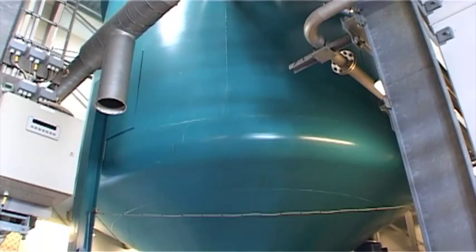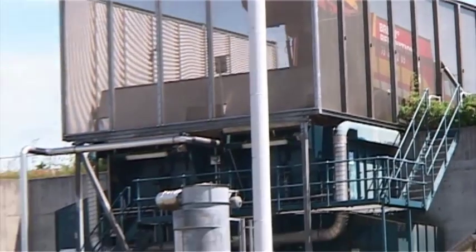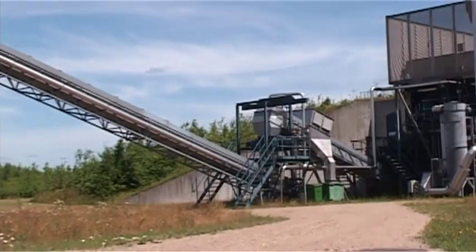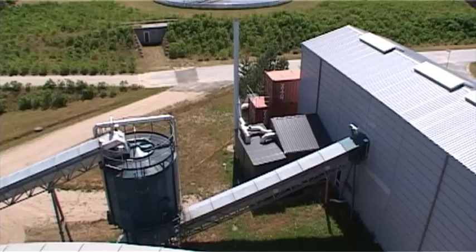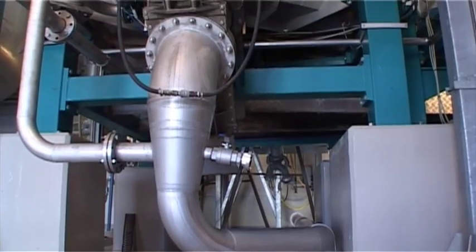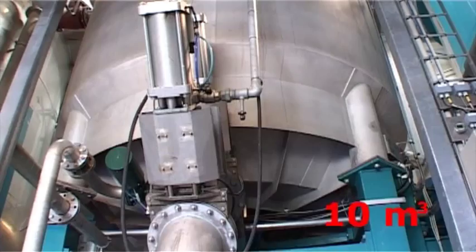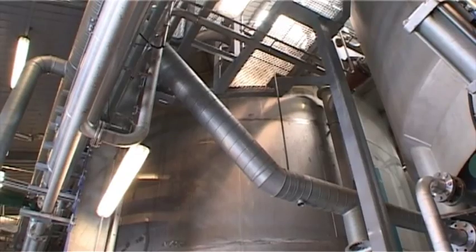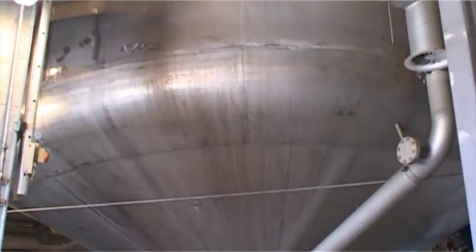Sewage slurry is pumped in from this tank. Food refuse is broken down in a two-phase process, which also involves magnetic separation. The processed refuse is then stored in a buffer tank, from which the precise amount needed can be transferred via a computer-controlled belt conveyor. Liquid industrial refuse is pumped from the industrial reception tank by injection into the mixed pulp from the pulper.